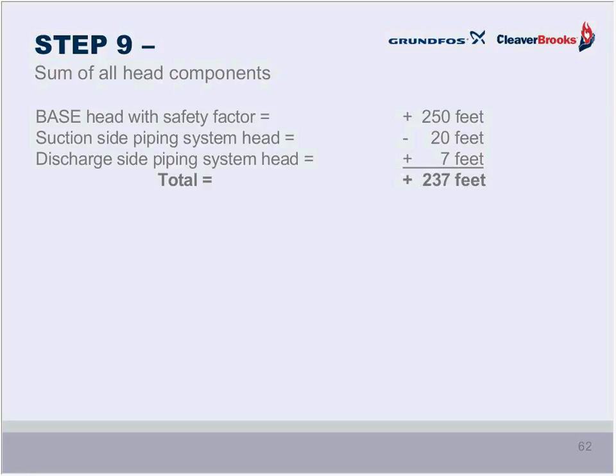feet. Now you might recall in the previous exercises the head calculation was 272 feet. That was primarily because of the feed valve, so you can see the advantage here of elimination of the feed valve through the use of direct control of a variable speed pump.